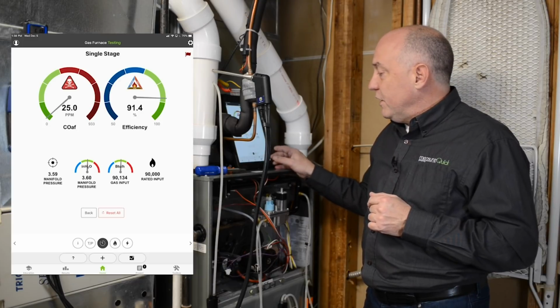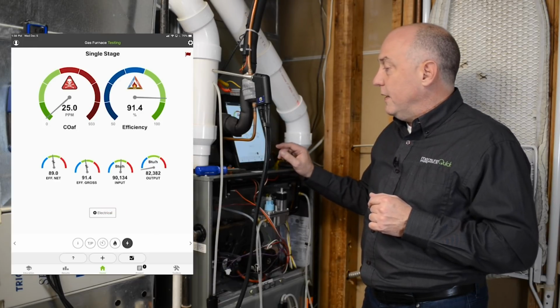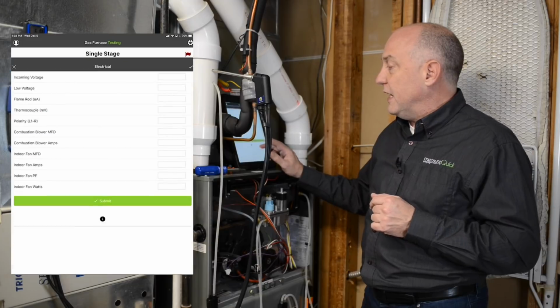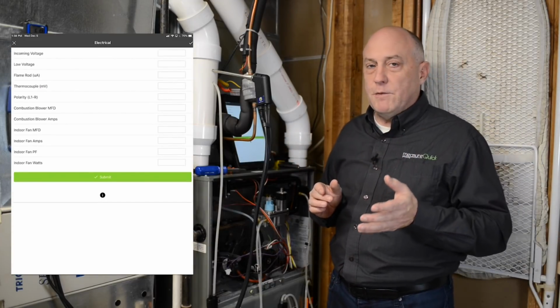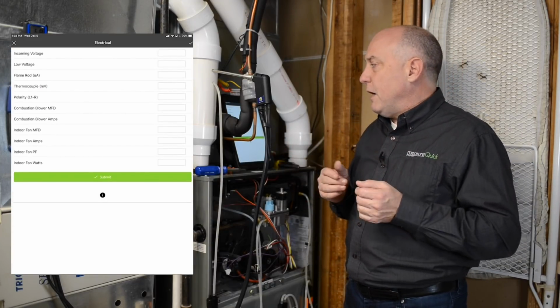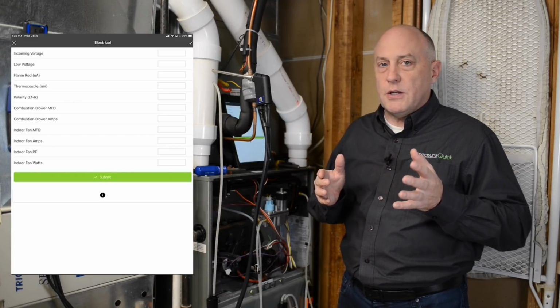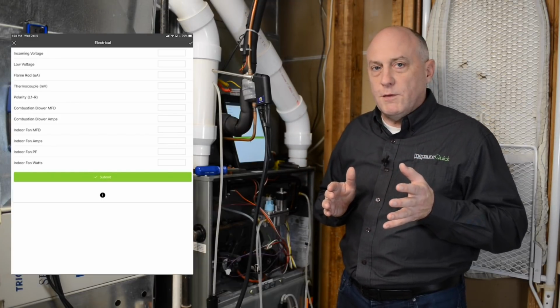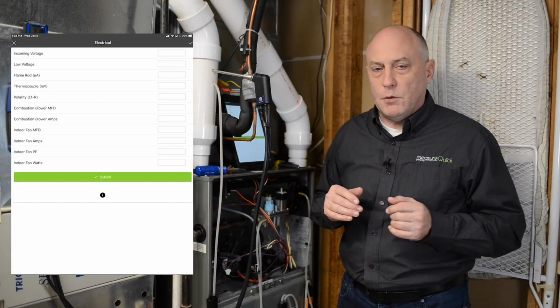Now the only thing we have left to do here is get some electrical readings. So if I go into the electrical section, this is where I can measure my incoming voltage, my low voltage, flame rod microamps, polarity, combustion blower. So I'm going to take a minute. I'm going to do all those voltage readings, and then we'll come back in and we'll print the report.